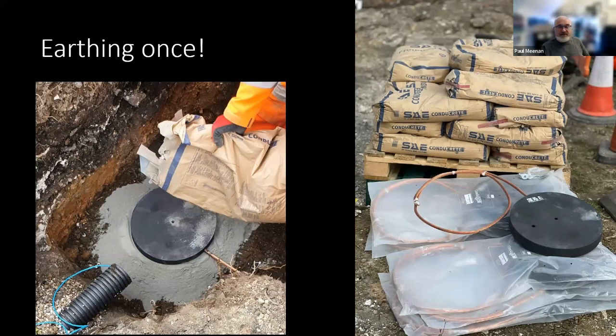One of my favorite things that I've recently been doing over the last few years is getting rid of rods, because they can be inherently dangerous, banging a rod into the ground and hitting a buried service, especially in England where the roads and the streets are quite congested. So I've been trialing some discs, which are carbon coated discs with a copper connection, from a company called Earthing Services. They're used in America at the bottom of telecoms poles to give a local earth reference, so similar to a rod but a lot safer. It just bolts onto the bottom of the pole.